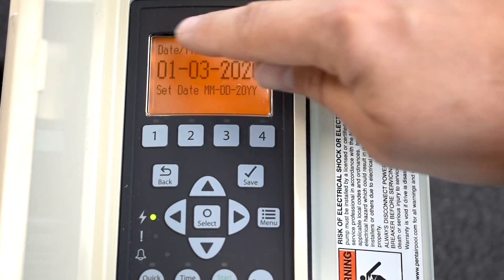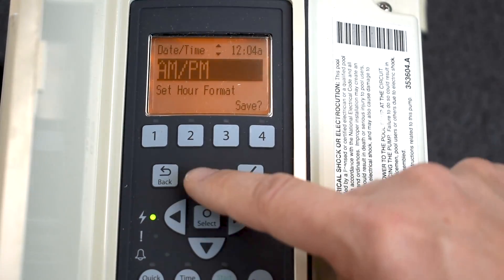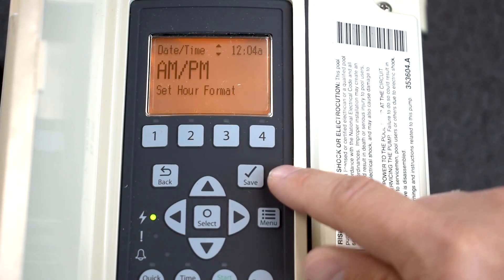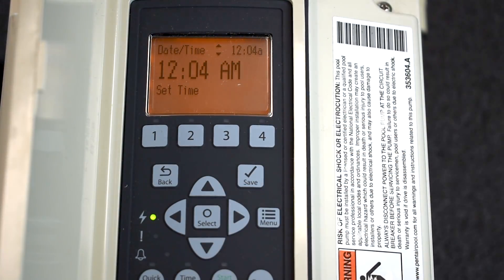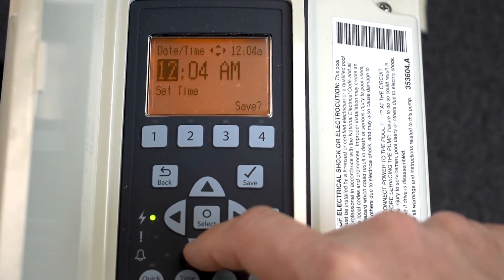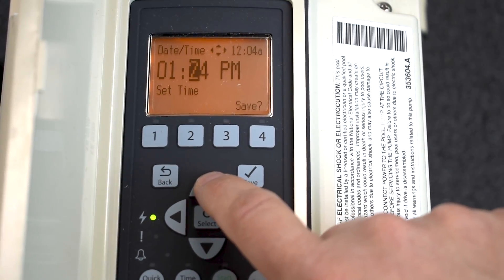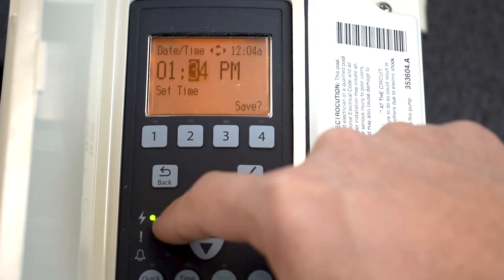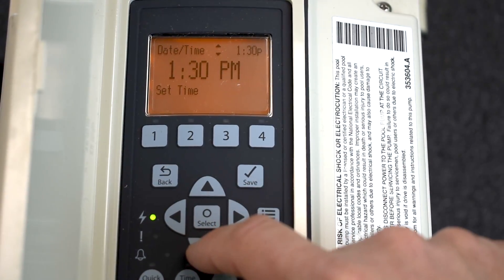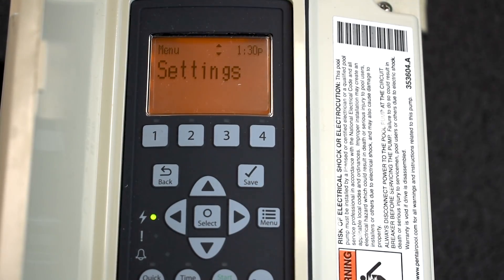Press the Up button — Date and Time has options at the very top to go to a different menu. You can change the hour format: AM/PM or 24-hour if you prefer military time. We'll stick with AM/PM and press Save. Go up again to Time and adjust it to your current time of day. Press the arrow over to navigate back and forth between mini menus. I'm going to set it to 1:30 PM. Press Save — not Select. That's all three of the date and time options. Press Menu to back out; everything is saved. That's how you set the date and time on IntelliFlo.